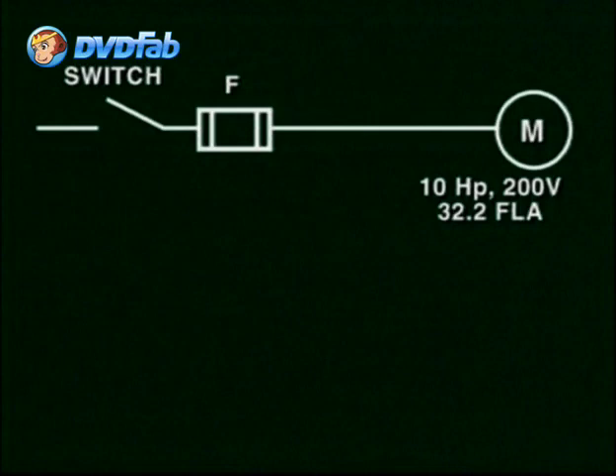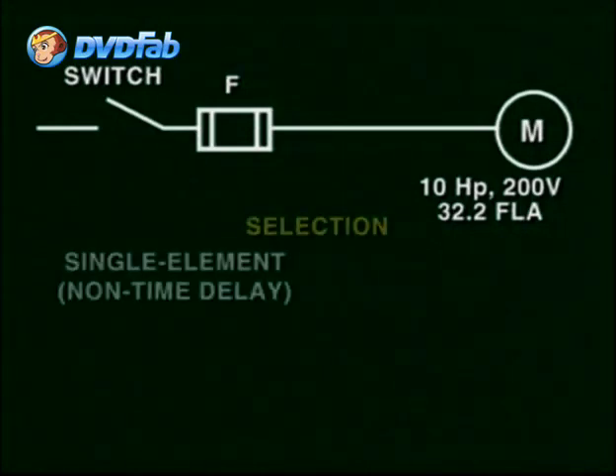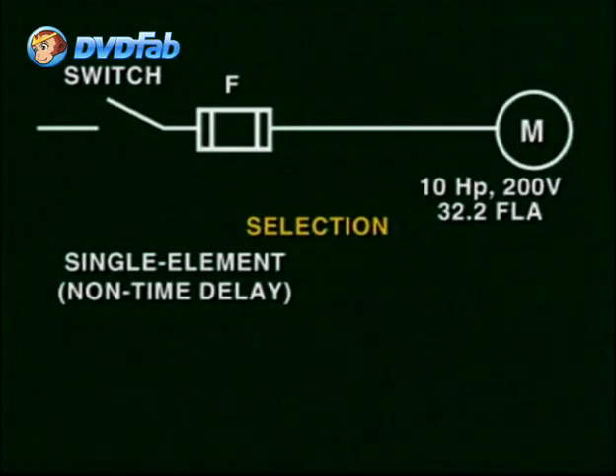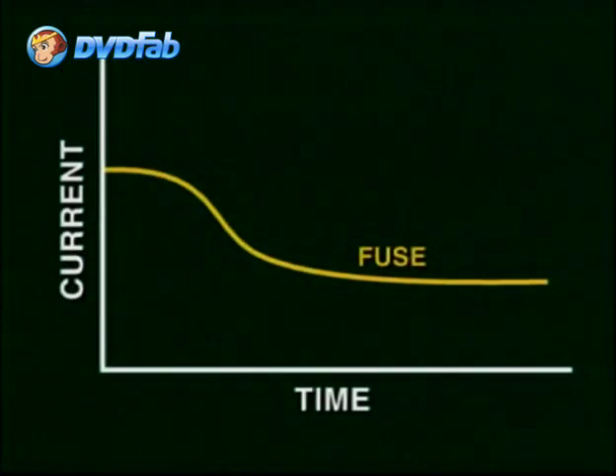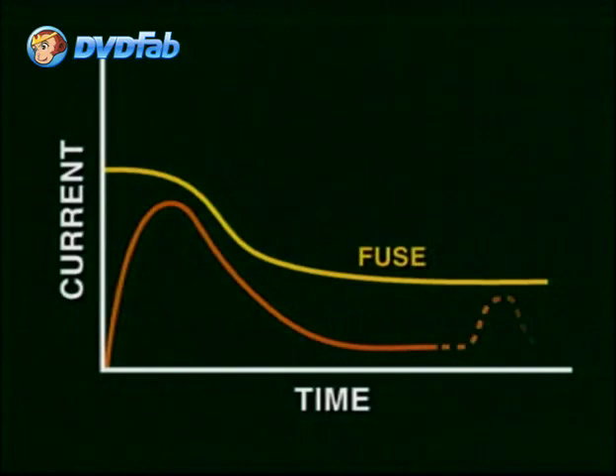Let's take a quick example using both single-element and double-element fuses for our 10-horsepower 200-volt motor. This motor has a full load amperage rating of 32.2 amps. According to the National Electric Code, we could select a single-element non-time delay fuse of 90 amps to protect the circuit, according to Rule 430-52 of the Code. This fuse should be enough to let the motor start for a short duration.